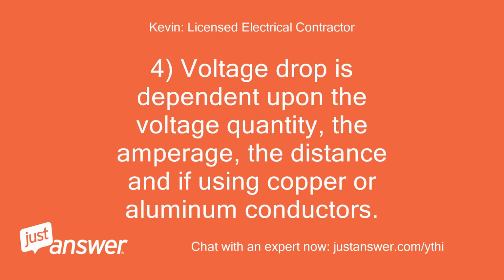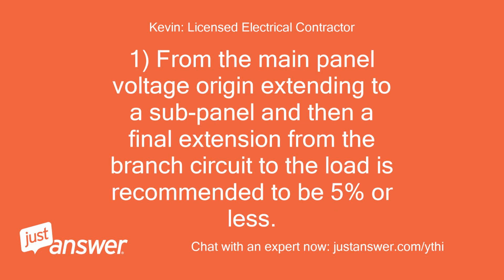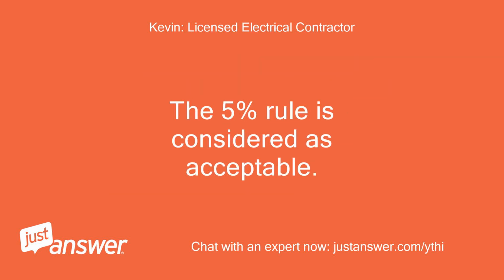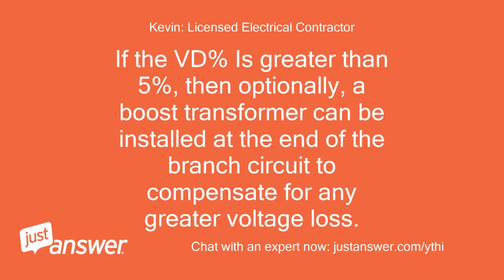4. Voltage drop is dependent upon the voltage quantity, the amperage, the distance, and if using copper or aluminum conductors. 1. From the main panel voltage origin extending to a subpanel and then a final extension from the branch circuit to the load is recommended to be 5% or less. The 5% rule is considered acceptable. If the VD percent is greater than 5%, then optionally, a boost transformer can be installed at the end of the branch circuit to compensate for any greater voltage loss.